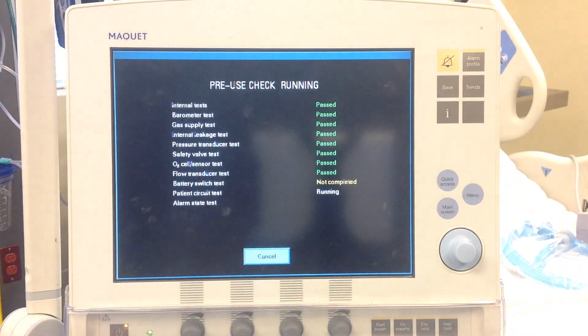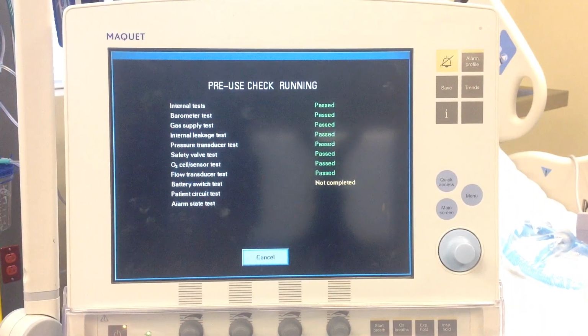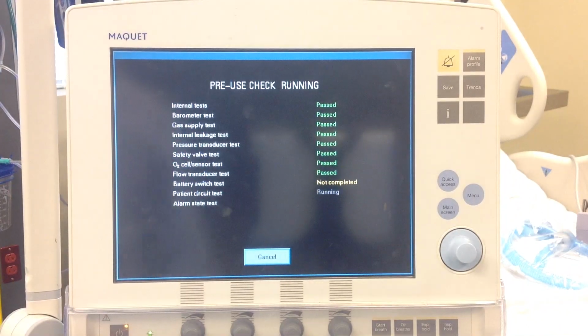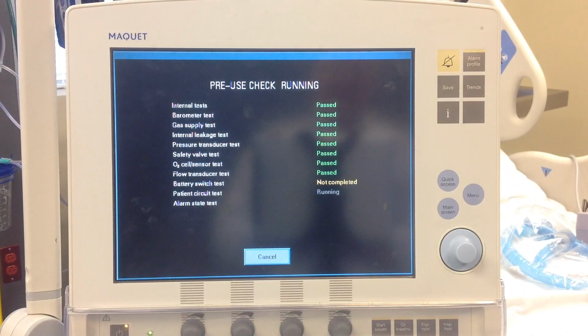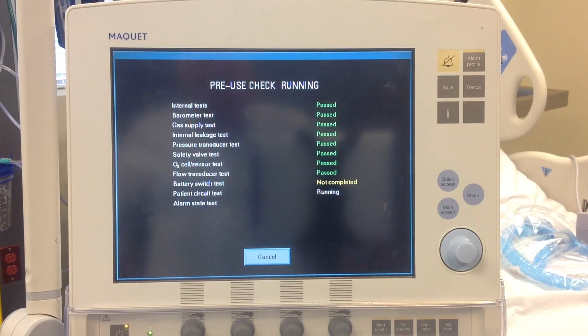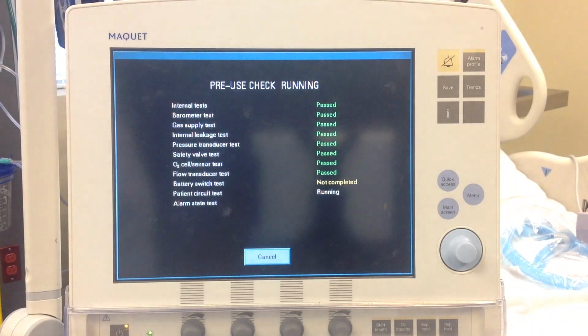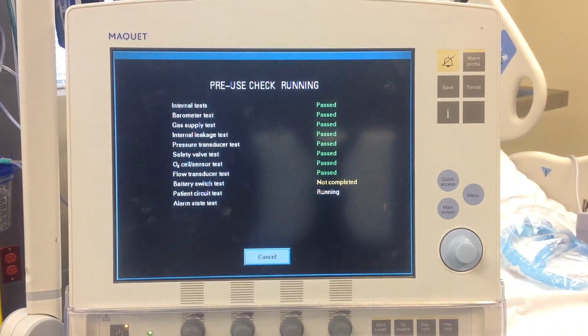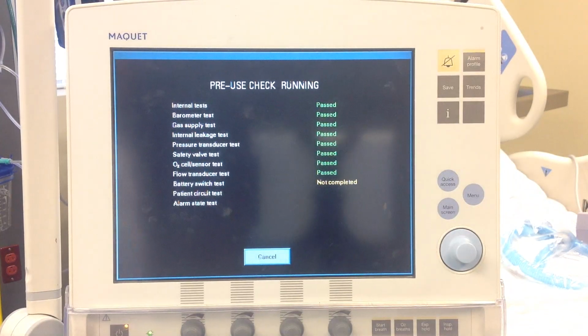There are 6 slots that you can fill all of them up with batteries, and technically you could run this ventilator on battery power for over 6 hours. So we're doing the patient circuit test, still waiting. And that battery is where the little slot is on the side. You can put in other modules, such as the Nava module, may go in there. Different modules that you could use on different patients.